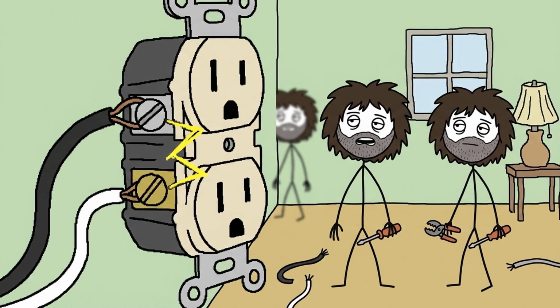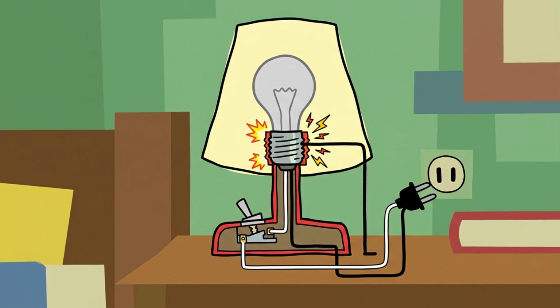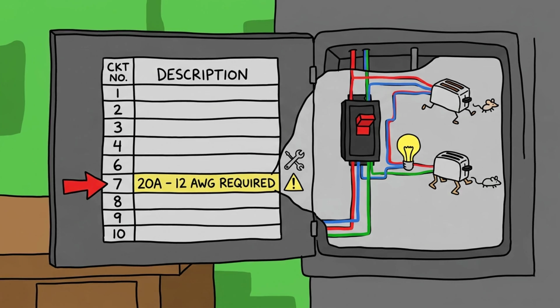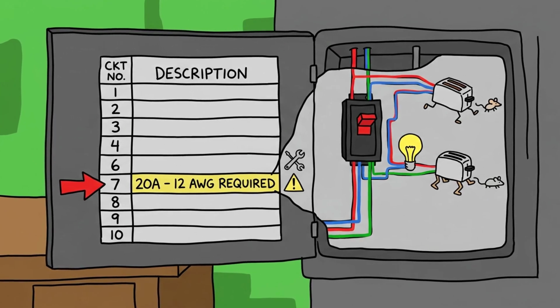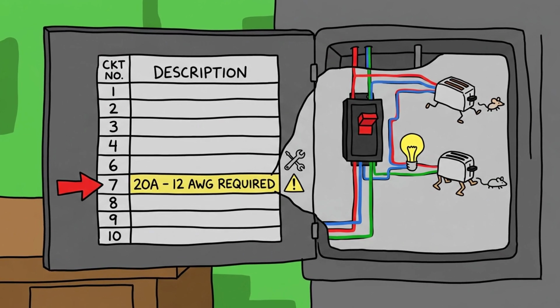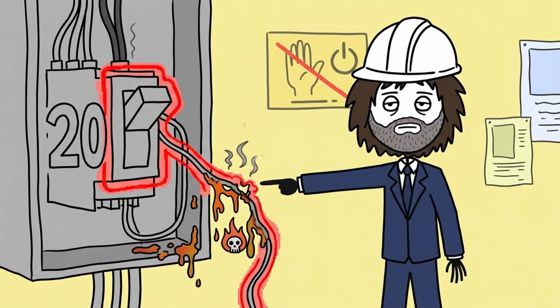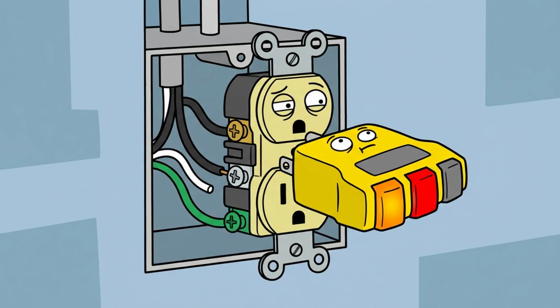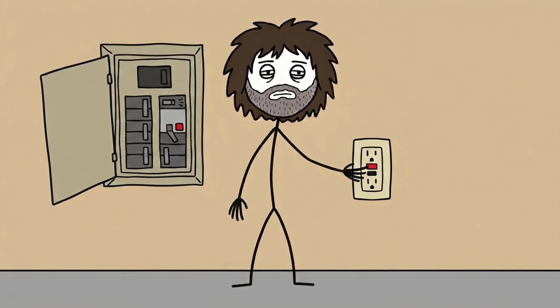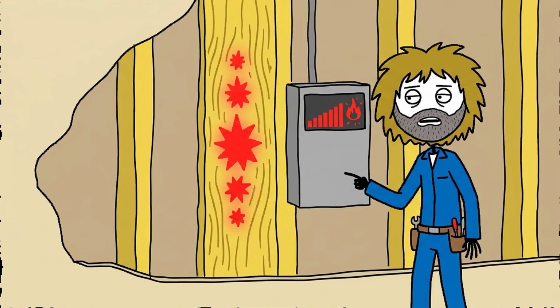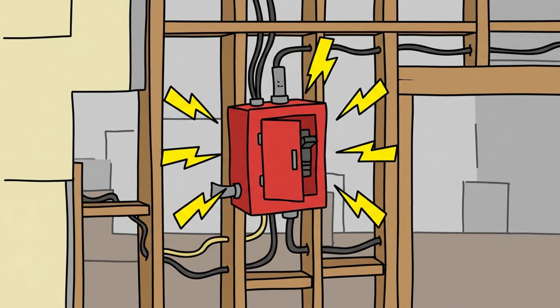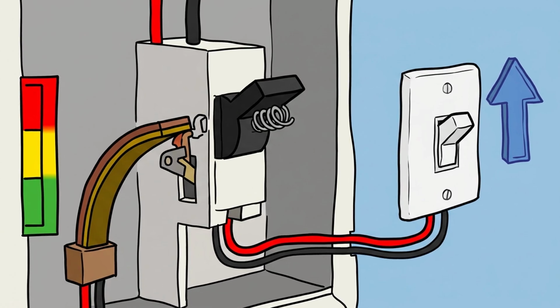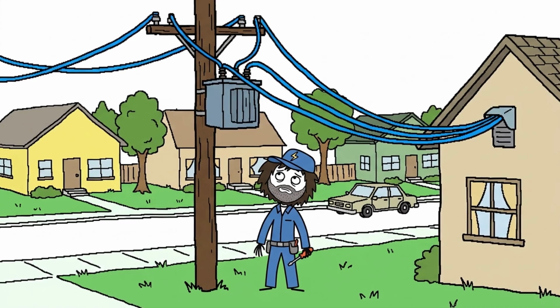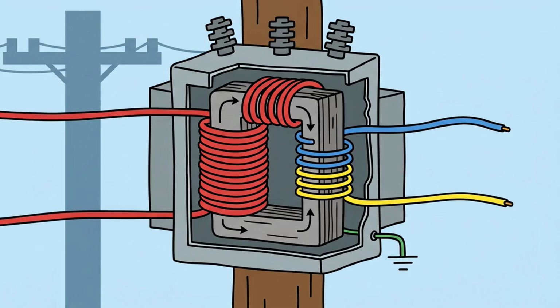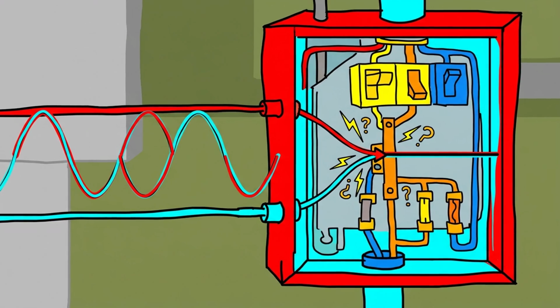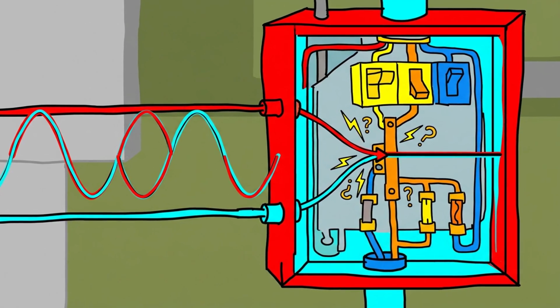Larger appliances require even thicker conductors. Clothes dryers use 10 AWG wire on 30-amp breakers, while central air units require heavy-duty 6 AWG or 4 AWG copper conductors on 50-amp double-pole breakers. Wire sizing relies on circular mil area and distance. As electricity travels long distances to a garage, it experiences voltage drop from cumulative resistance. If a circuit runs over 100 feet, voltage drops significantly, forcing connected motors to draw higher amperage to maintain power output. This extra amperage generates dangerous thermal buildup. Thicker wire gauges lower total resistance, keeping voltage stable and preventing thermal degradation along the entire cable run.